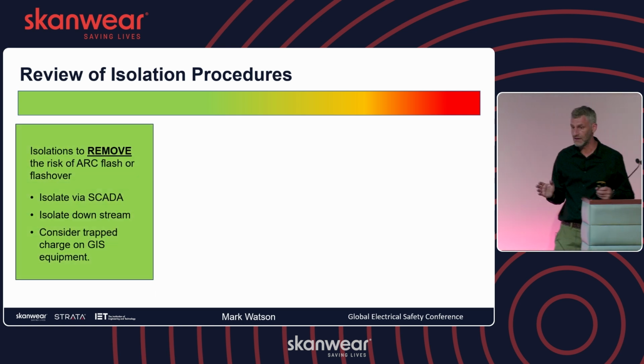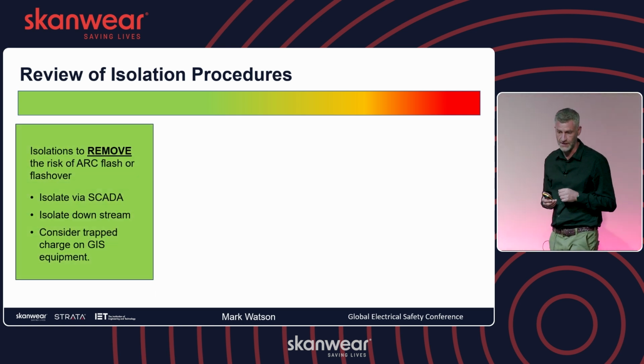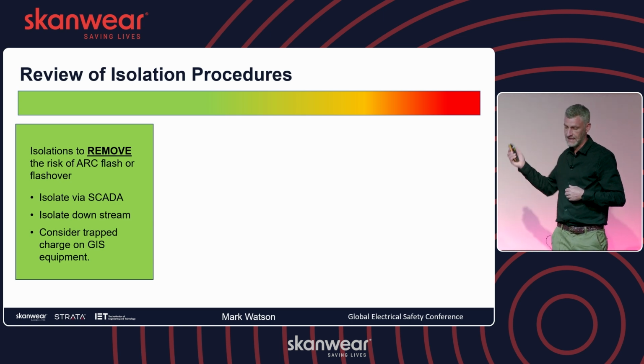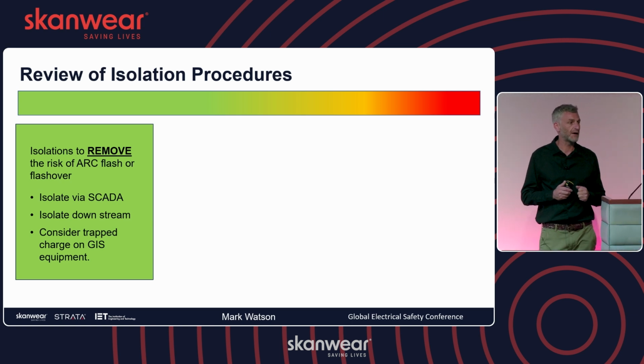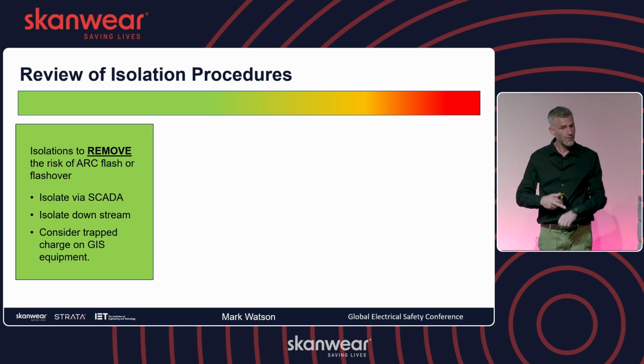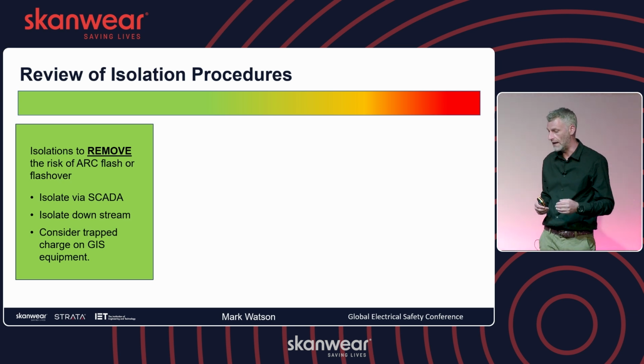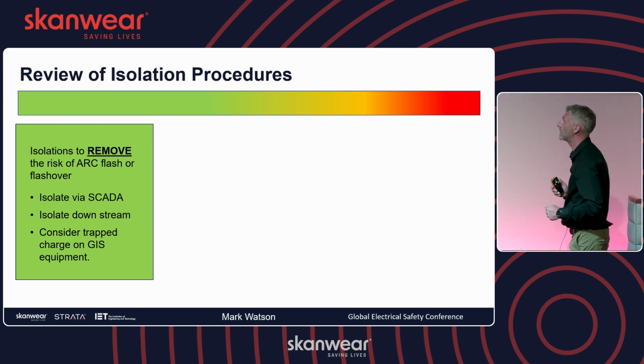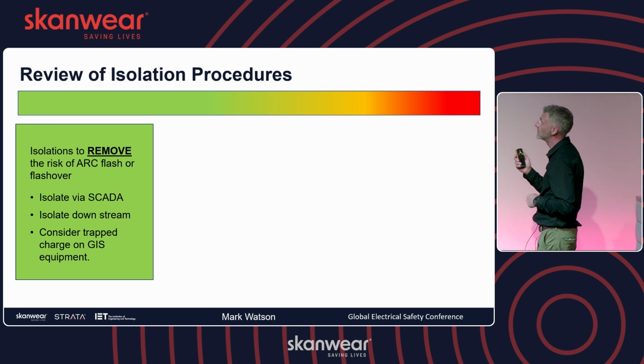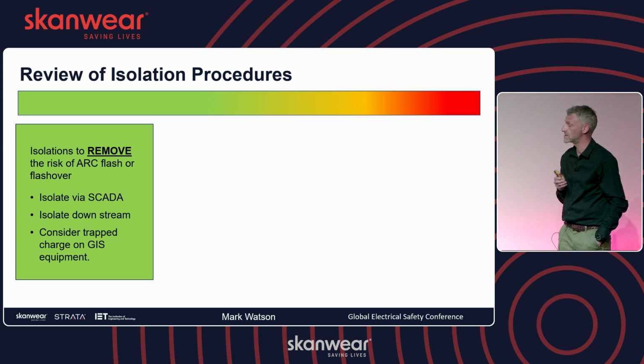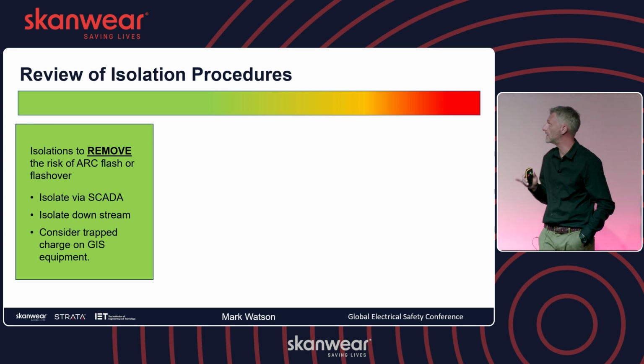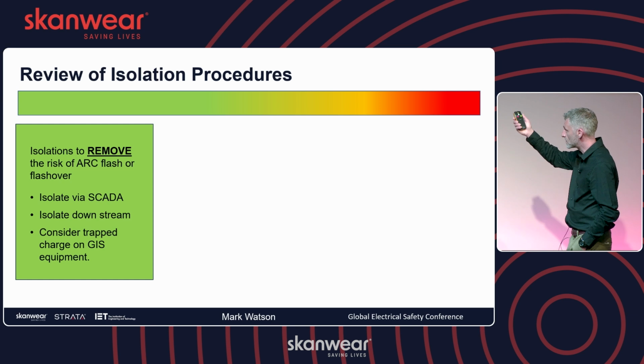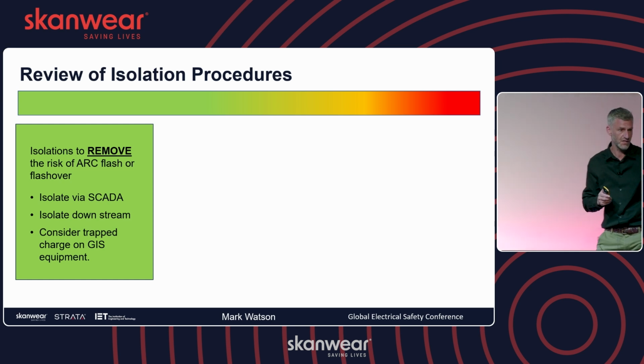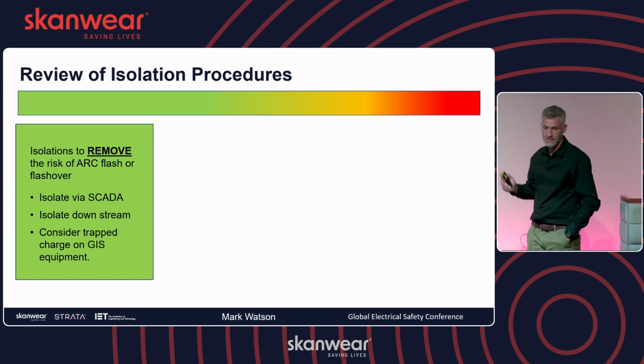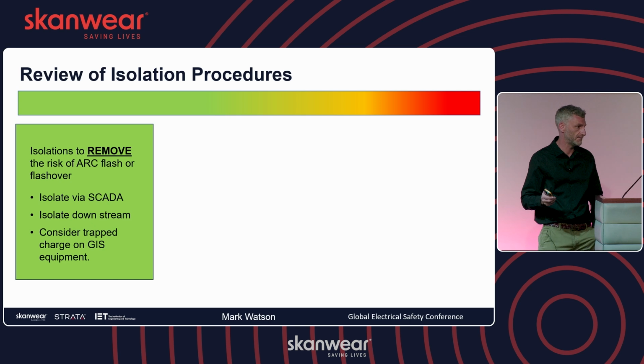We talked about arc flash. There's a risk, and you don't want to expose people to it. It's exactly the same as what we're discussing now around this hierarchy of control. We just want to keep people out of the way, so we want to see if we can remove the risk. We consider isolations to remove the risk of arc flash - fundamentally, that's what we want to do first. So we consider the hierarchy of switching. You've removed the risk of arc flash if you're nowhere near it.